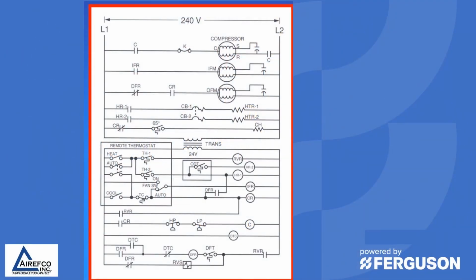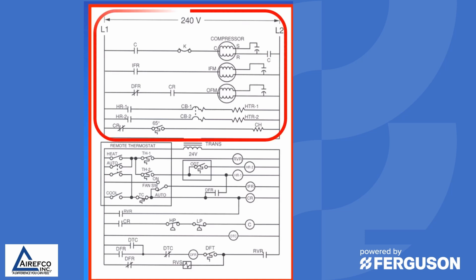In this video, we're going to talk about reading wiring diagrams. This is a typical ladder wiring diagram. It has the high voltage at the top. In this case, it's 240 volts with compressor, fan motors, and other relays. And the bottom is divided by the transformer, where you have a 24-volt circuit. So all of your relays and thermostats are controlled by 24 volts.